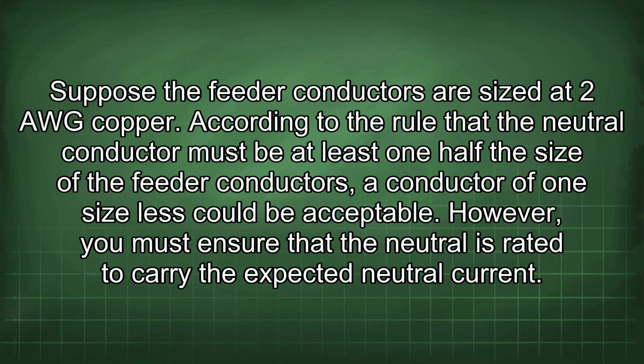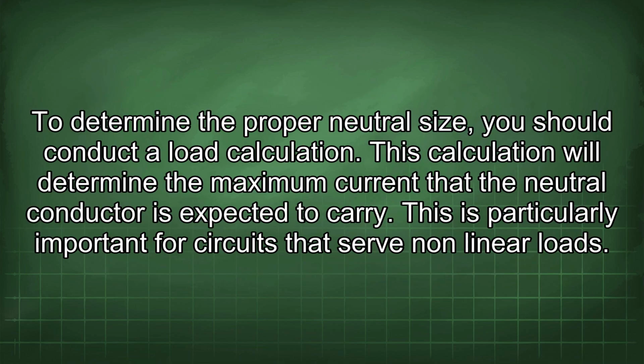Suppose the feeder conductors are sized at 2 AWG copper. According to the rule that the neutral conductor must be at least one-half the size of the feeder conductors, a conductor of one size less could be acceptable. However, you must ensure that the neutral is rated to carry the expected neutral current. To determine the proper neutral size, you should conduct a load calculation. This calculation will determine the maximum current that the neutral conductor is expected to carry.